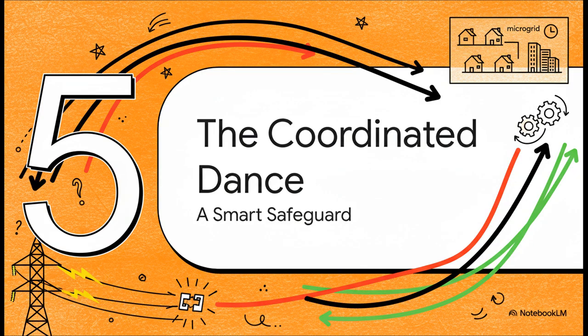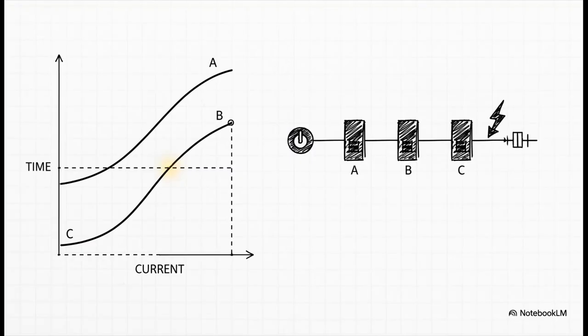and reliably. See, across the entire grid, each one of these protective devices is carefully graded. This means that response curves are intentionally stacked and timed relative to each other. By coordinating the curves of all the devices upstream and downstream, engineers create this cascading defense that makes sure only the device closest to the fault operates, and for exactly the right reason.